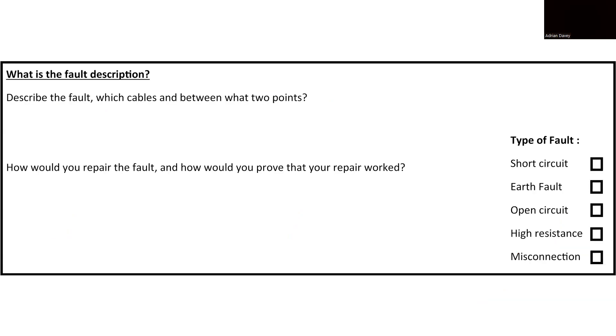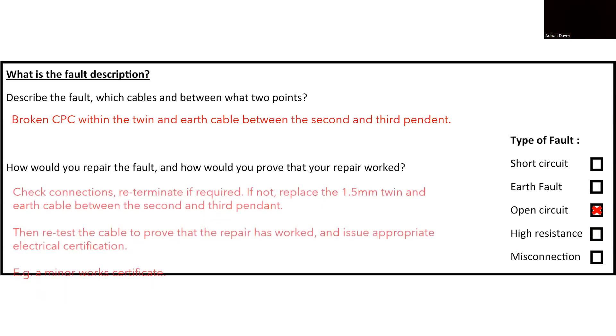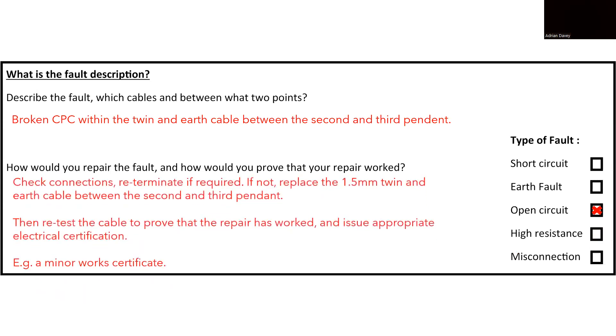If we were required to write a report on the fault to provide feedback to the person who requested the work, the report could be structured as following. A broken circuit protective conductor has been identified between the second and third pendant. This issue allows us to classify it as an open circuit, and to rectify this, we can replace the 1.5 mm twin-and-earth cable running between second and third pendant, since the CPC is an integral part of this cable. If the circuit was wired using single-core conductors enclosed in trunking or conduit, we would simply replace the individual cores.